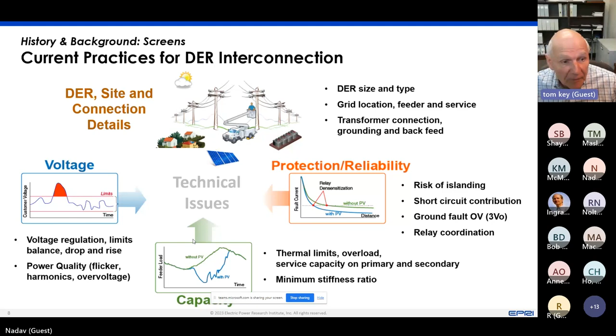There's quite a bit of detail, and that's what I was going to go into. If we go on to the next slide, Nadav, there are a number of things that you need to look at as the penetration grows and the size of the systems increases, and then of course there's complexity, let's say, of adding energy storage and systems that are just more complex. So we try to categorize it here into 4 areas. Location matters probably the most, whether it's close to the substation or further away, and there's some criteria on that even in the SGIP. Usually the first thing that needs to be looked at is voltage impact and thermal, which we also call capacity: does the system have the capacity to handle it? And then when the increase in fault current gets to a certain level, checking the protection coordination is becoming a more important issue as the aggregate number of systems or the overall fault contribution increases.